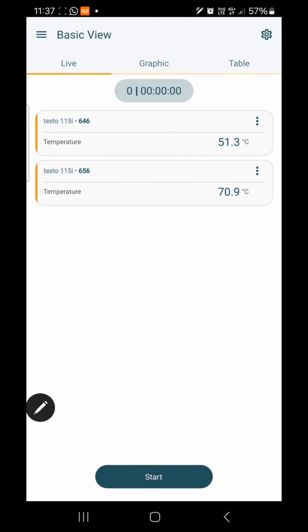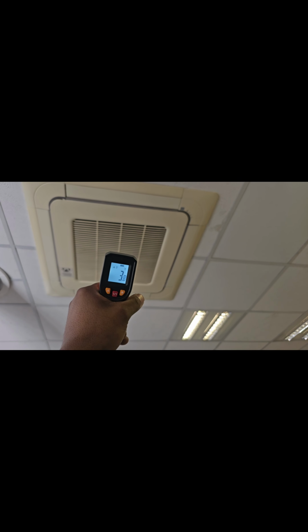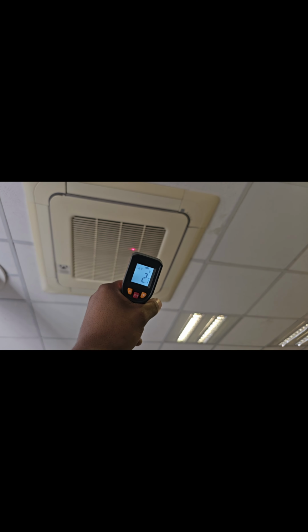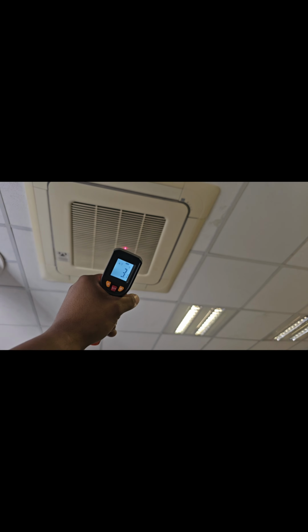Alright, so 646, the top one, is on the low side, and 656 is on the high side. So not exactly identical, but obviously you can see that low side is 50 degrees Celsius. Definitely a problem. Okay, so as you guys can see, I can feel an extreme cold. The air is extremely cold dropping from this unit. So that one's not running either. Neither is that one, nor is that one. Essentially everything on the ground floor is not running, and then we've got one unit on the first floor not running.